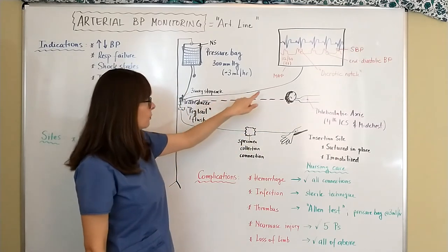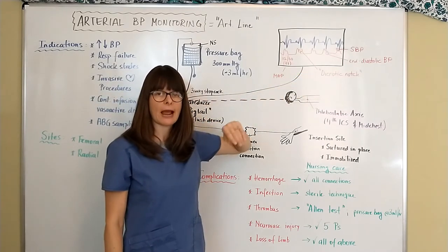So we always need to make sure that this is lined up with the phlebostatic axis and then from the transducer we have a wire that is hooked up to our monitor that gives us the output of what we are actually monitoring.